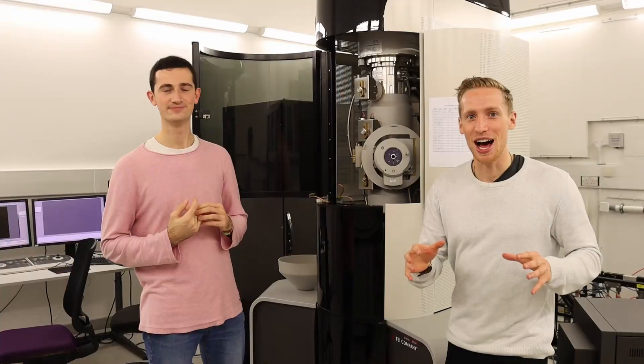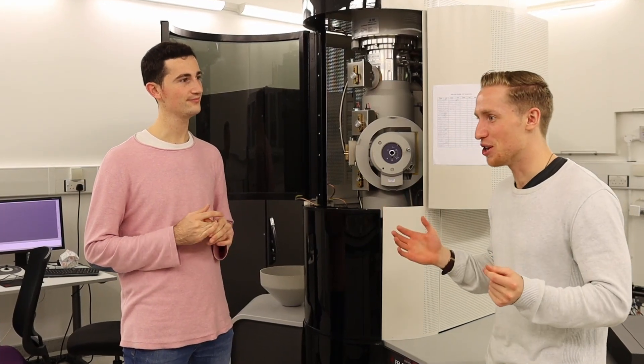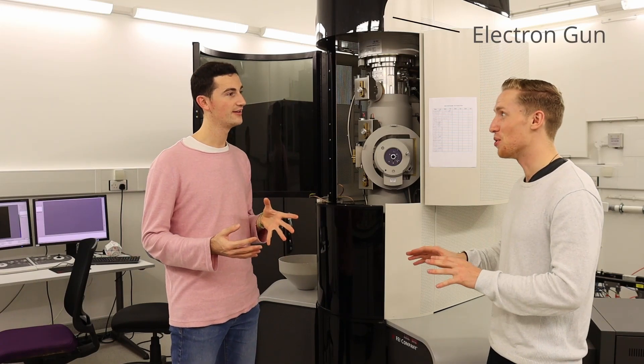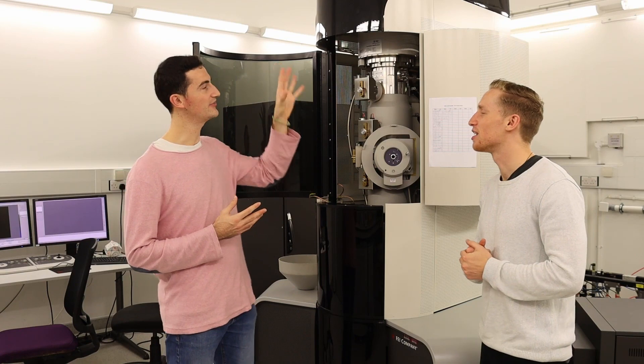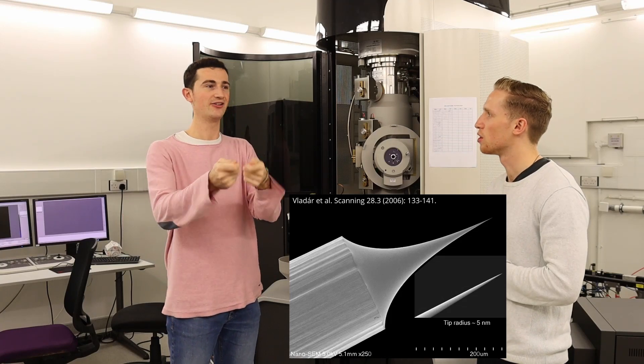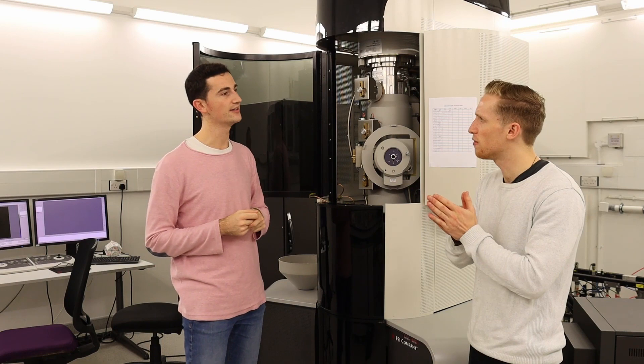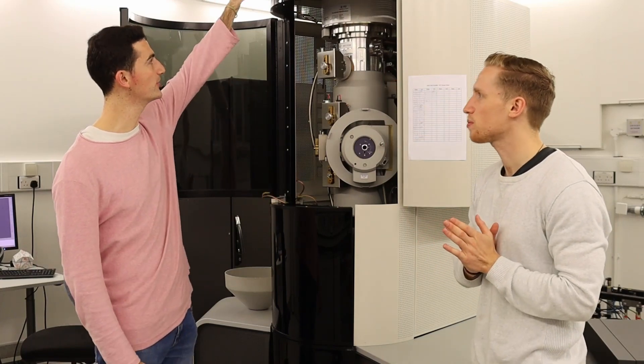Now we're back at the machine we're going to use for measurements today, which allows you to see individual atoms — essentially the ultimate resolution of any microscope. How does this thing work? It all starts right at the top at the electron gun. When you say electron gun — it's an analogy. At the end of the day, what we have there is a very sharp tip where we apply some voltage, some energy, and from there we can accelerate electrons. These electrons come out from the tip at very high energy, continuously and spontaneously when you apply small voltages.